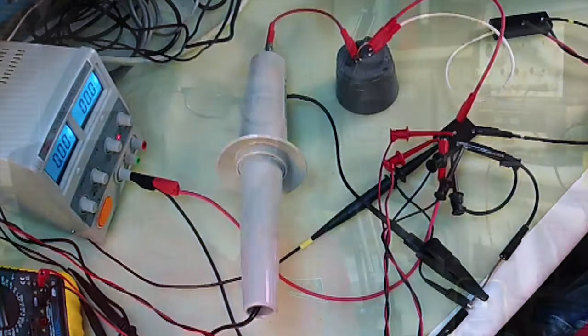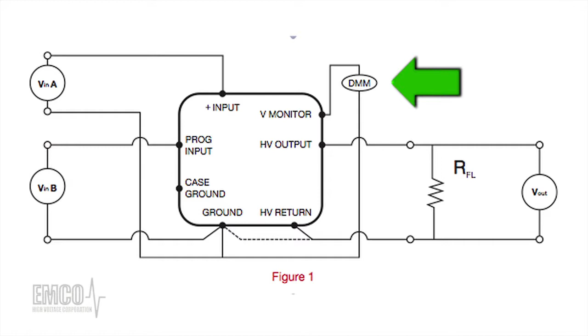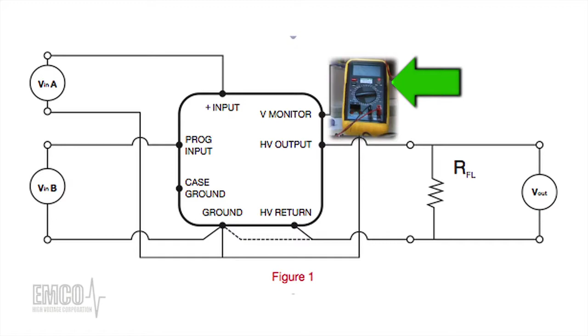Another piece of equipment necessary is a DMM to monitor the voltage monitor pin. Most of our regulated supplies provide a voltage monitor that gives a low voltage representation of the high voltage output, proportional to it. The ratio depends on the model, so consult the data sheet to find out exactly what that voltage should be.